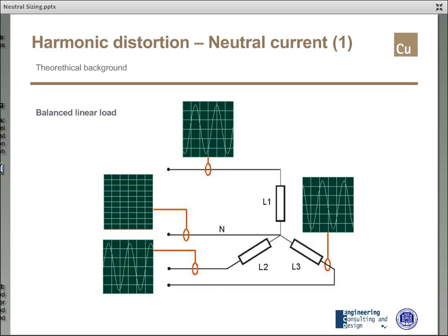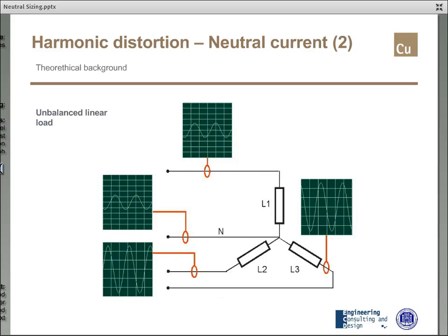Don't worry, I discovered quite soon the reason. By the way, with the balanced linear load, no current into the neutral. And from this, the practice and also the general prescription of the standard to reduce the section of the neutral. Let's consider now an unbalanced linear load. In such a case, I have a current in the neutral, not zero, but is still less or...